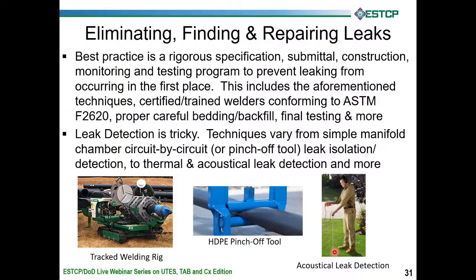But in essence, the key techniques to use with that are to isolate it down to the circuit that you've got there. In addition to the water makeup, you attach a high volume, low pressure air compressor and mix air in there with it, so that you end up not just with water spraying into the dirt or just air hissing out, but a gurgling, kind of violent situation there at the leak where water and air are both gurgling out at the same time. And they basically go along the markings on the ground until the noise hits the highest level and then dig down and find the loops. And he said they have found that 12 out of 12 times.